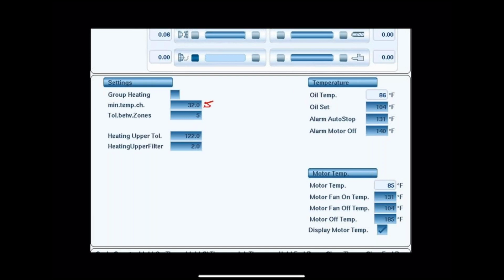Then you'll have a minimum temperature change, so it'll keep that tolerance pretty tight for 32 degrees. So if you want it even tighter, you can actually lower that to whatever temperature you want the minimum temperature change to be. And here's the tolerance between zones of 5 degrees. You have your upper tolerance and your upper heating filter.